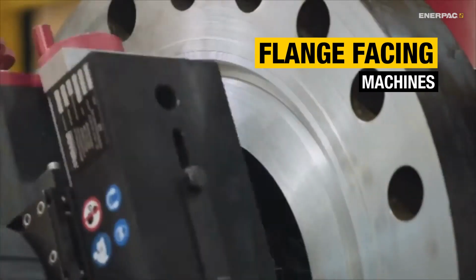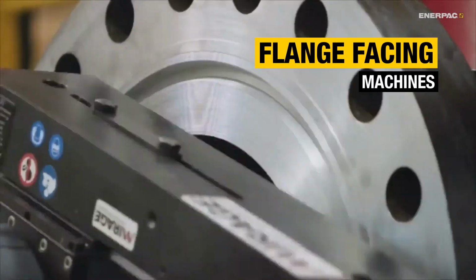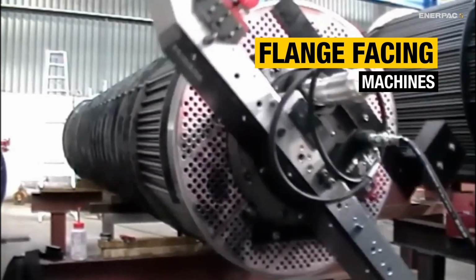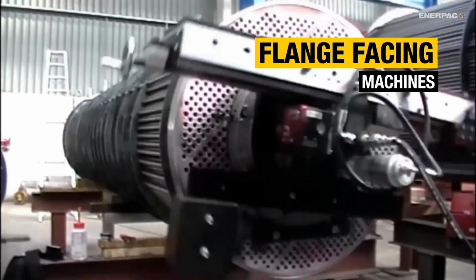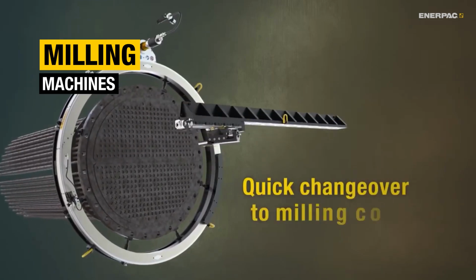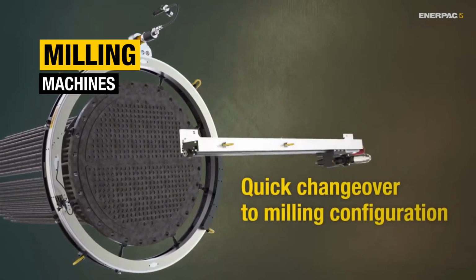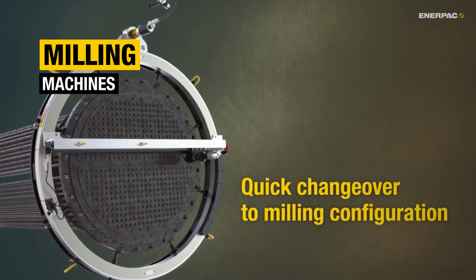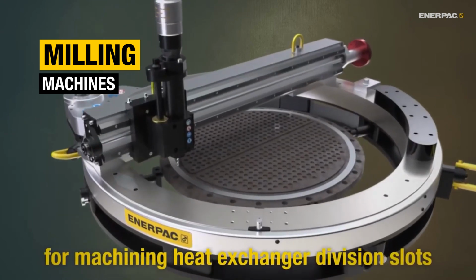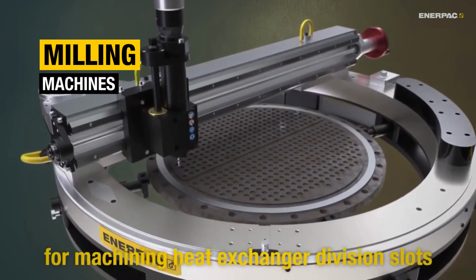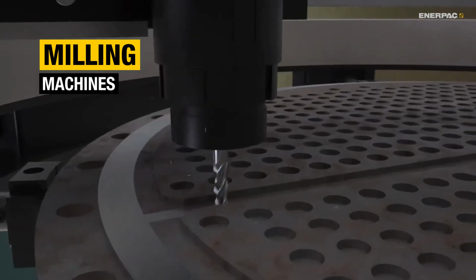That's why on-site machining teams rely on flange-facing machines to restore sealing surfaces on pipe flanges and on heat exchangers. And milling machines can be used on the end faces of heat exchangers to precisely resurface corroded division slots. This ensures a tight seal and correct flow distribution of the steam inside.